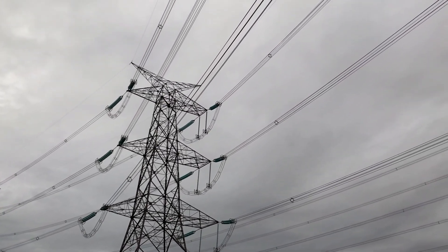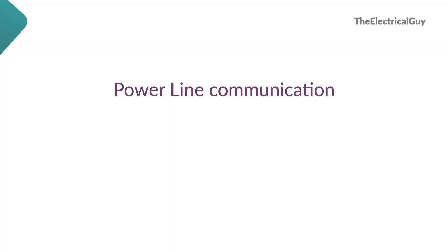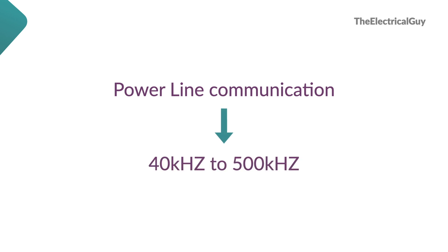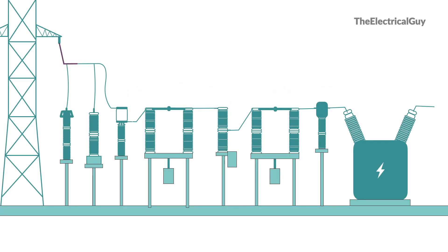Now to distinguish, communication signals are always delivered at very high frequency. That frequency can be 40kHz to 500kHz depending on the application. Now if these high frequency communication signals enter any substation equipment, which is designed for either 50Hz or 60Hz, it can damage the equipment.